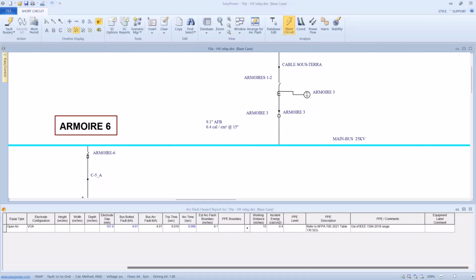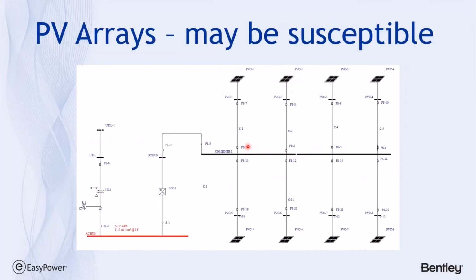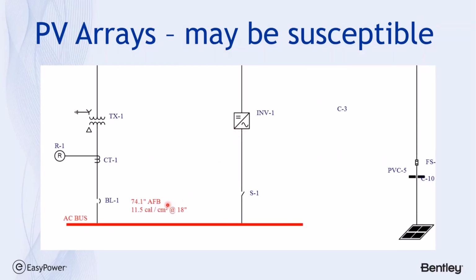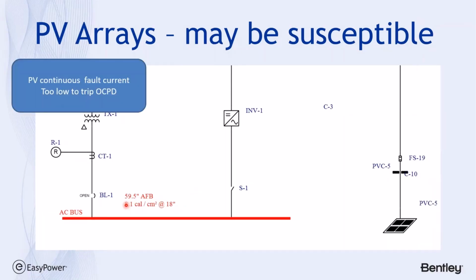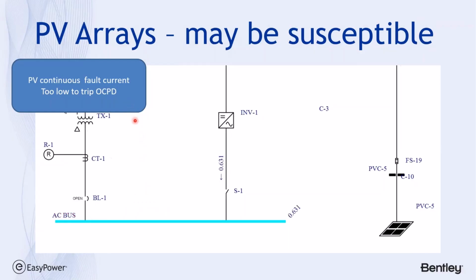So this phenomenon, I guess is what I would call it, is something that we should be aware of when we have constant energy sources that don't necessarily clear during the 2 seconds, because they don't shut off. Their fault current is lower than the protection that's installed in the system. So in this case, with the utility open, we still have an 8-calorie exposure because we have too low a current coming out of the photocells. And this would be where the 2-second limit would be appropriate for faulting on this bus with this low current.